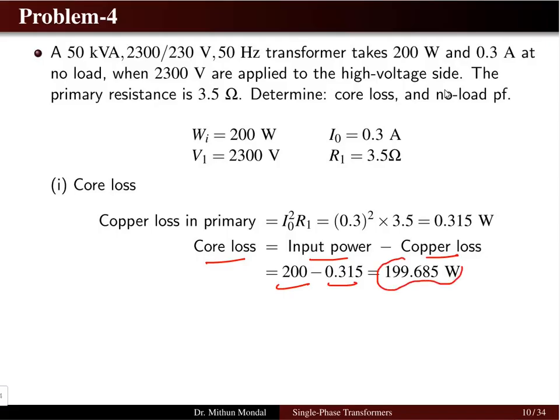Now note here, the input power is 200 watt and the core loss we are getting is 199.68. It means that the copper loss in the primary side we can neglect, and directly we can say that whatever the wattmeter reading shows under the no load condition is basically the core loss only. However, in this problem, we have solved it and proved that yes, the wattmeter reading is the core loss only.